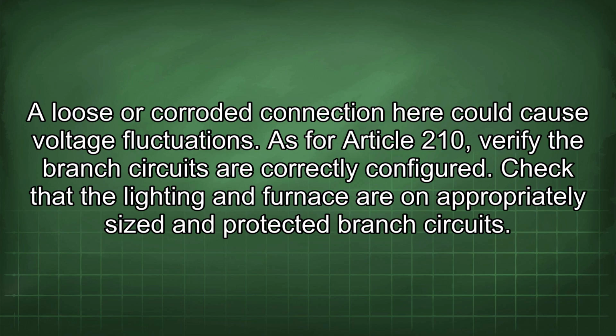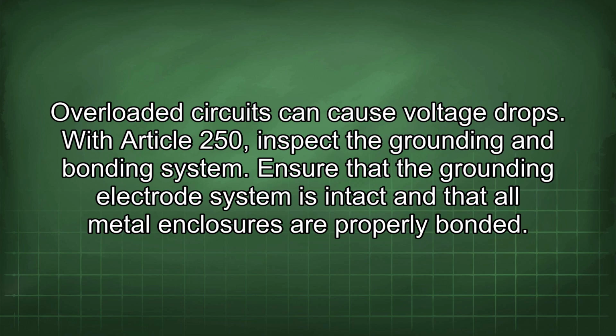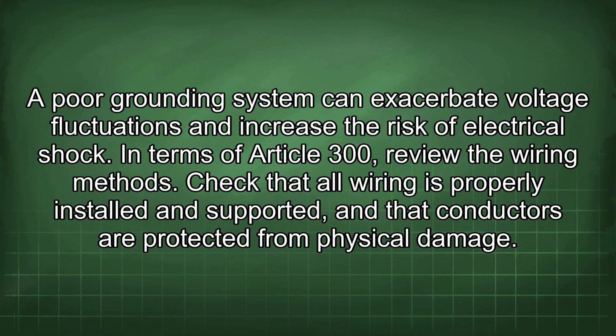As for Article 210, verify the branch circuits are correctly configured. Check that the lighting and furnace are on appropriately sized and protected branch circuits. Overloaded circuits can cause voltage drops. With Article 250, inspect the grounding and bonding system. Ensure that the grounding electrode system is intact and that all metal enclosures are properly bonded. A poor grounding system can exacerbate voltage fluctuations and increase the risk of electrical shock.